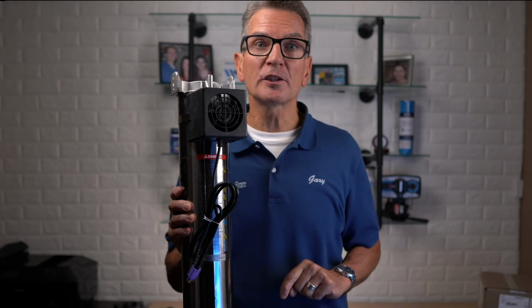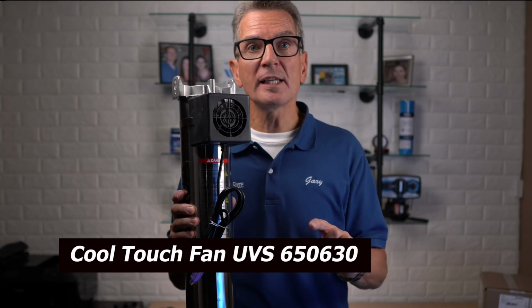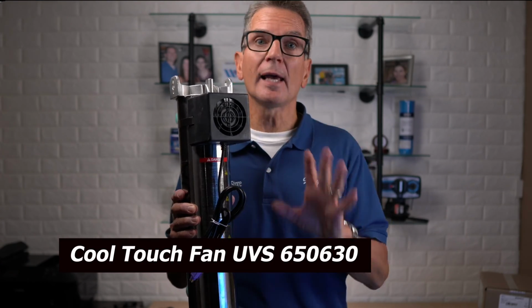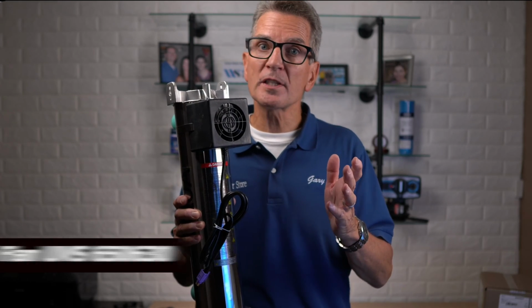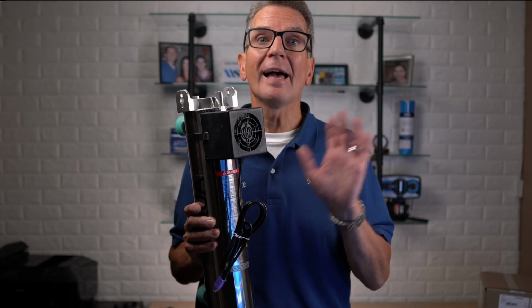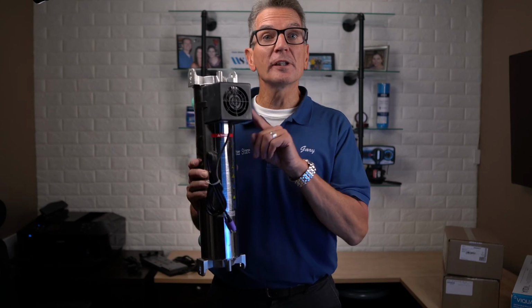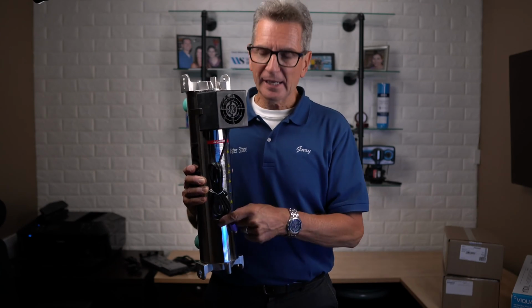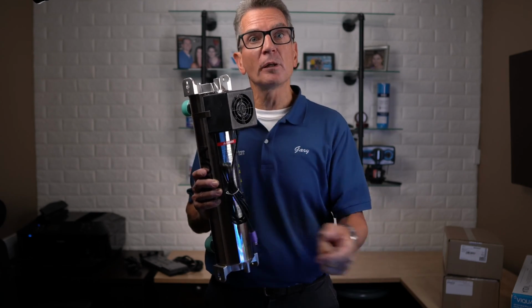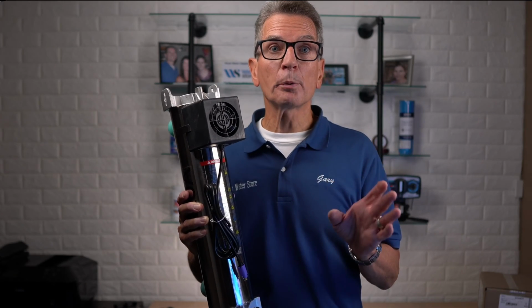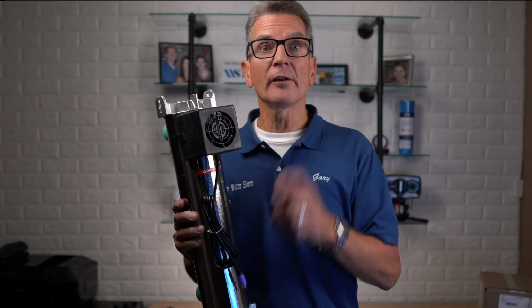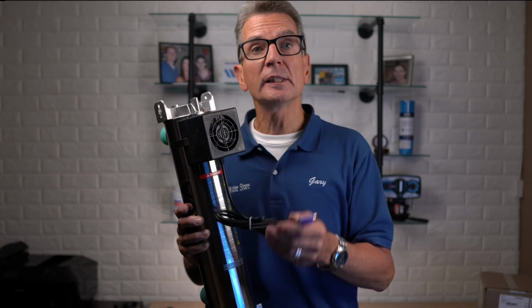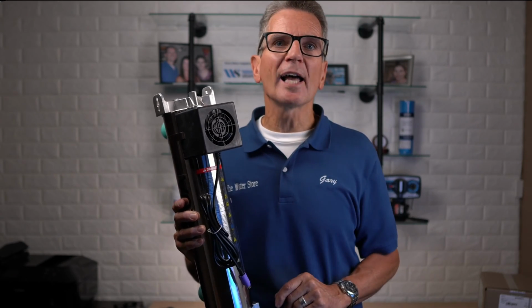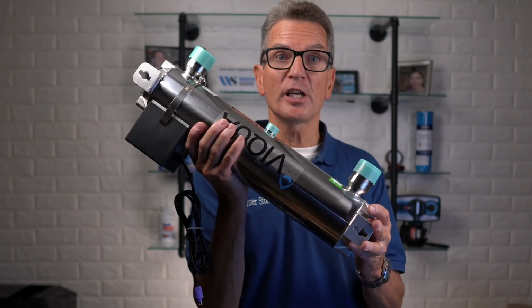Next up is the cool touch fan, which helps minimize the temperature inside the chamber. And again, what that does, it minimizes the amount of scaling that takes place on that sleeve, again, reducing maintenance. The cool touch fan is the same in all models. And again, you can see it's color coded to plug it into the controller. And the controller provides troubleshooting information to tell you if the cool touch fan is unplugged, if it's dirty, or if it needs recalibration.